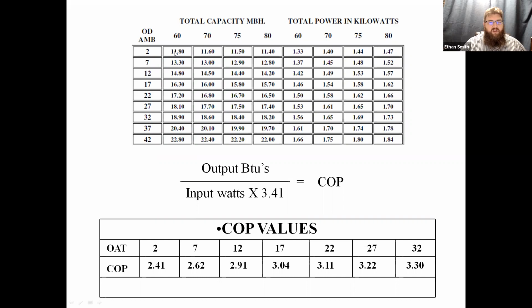And we would just do this every year. Well, the COPs didn't change typically, but we do this for our systems that we installed a lot of. So our typical SEER ratings would give us generally the same COPs. So we could go in at the beginning of the year and use our existing COP charts, and we'd have our break-even COPs. So the way you do this is you just calculate a COP for various points on your chart. So we did 2, 7, 12, 17, 22, 27, 32 on this particular one.